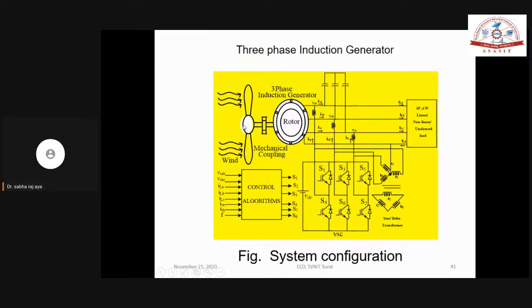If the turbine and this generator have somewhat nearby torque, and we have some constant rated voltage, assume that. Suppose a small variation is also there. The small variation is going to be taken care of by the battery. If load demand is going to decrease from the rated value, maybe 10%, 20%, 30%, or 40%, in that case our voltage is going to increase, and the frequency is going to increase. Up to how much? That depends upon how much the power has decreased.